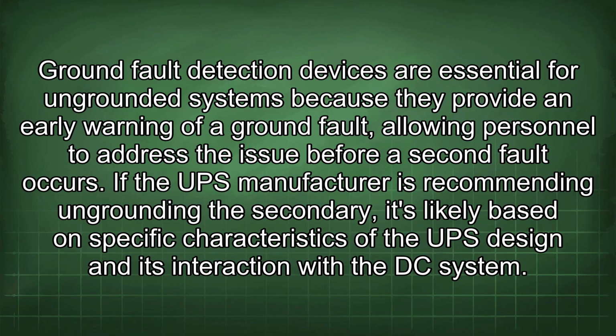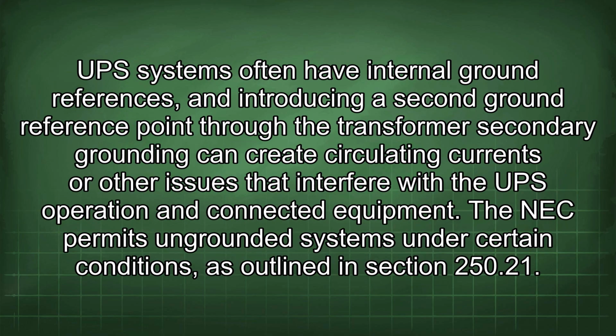If the UPS manufacturer is recommending ungrounding the secondary, it's likely based on specific characteristics of the UPS design and its interaction with the DC system. UPS systems often have internal ground references, and introducing a second ground reference point through the transformer secondary grounding can create circulating currents or other issues that interfere with the UPS operation and connected equipment.